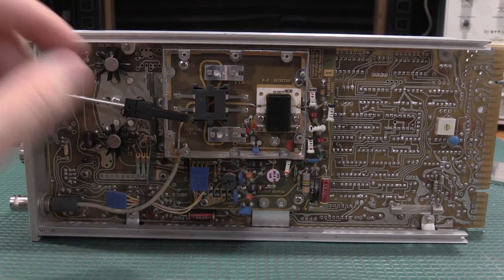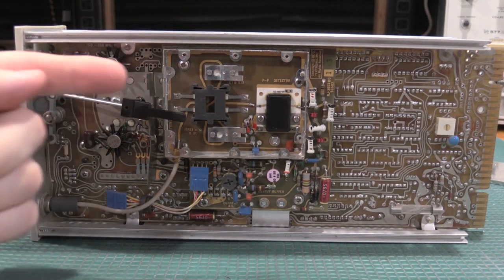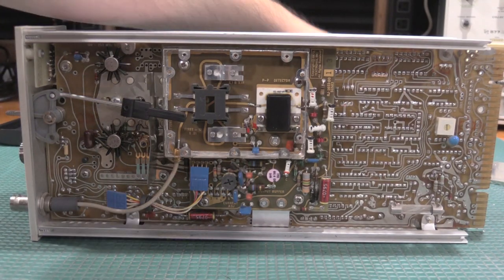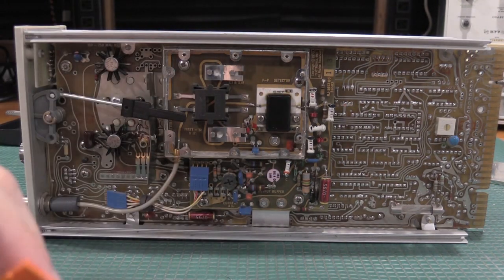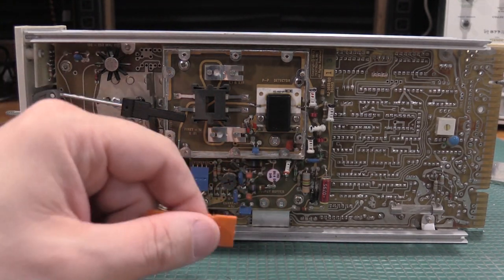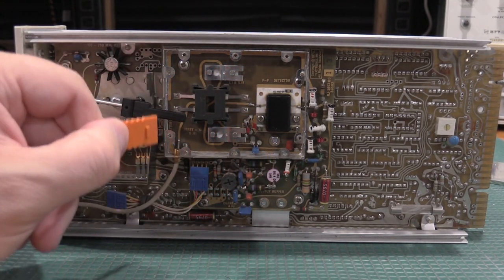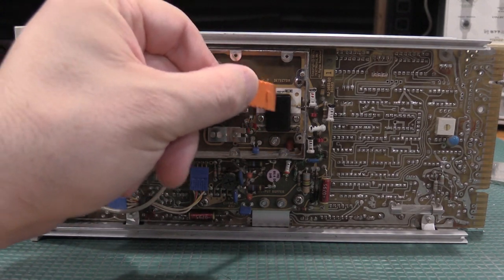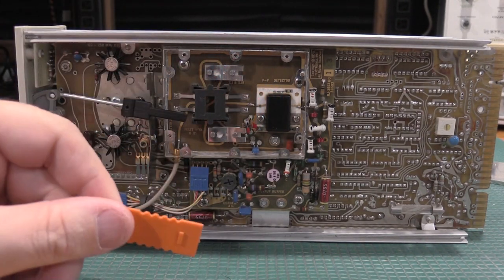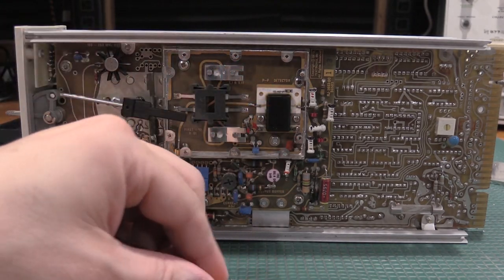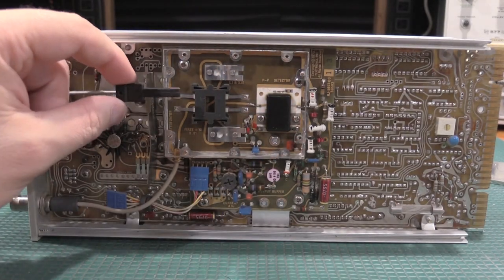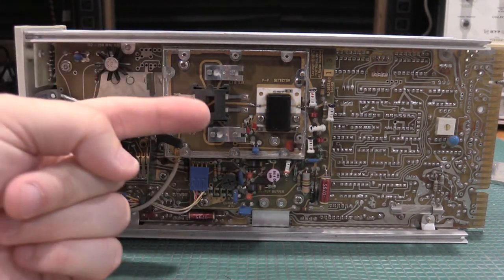Okay. I've got the switches exposed here. This is where that cam switch lever was. That moved that in and out. I did not need to take the peak-to-peak detector board out. You have to be real careful with this board. There's a lot of 50-ohm RF components on this board. This transistor. Given the circuit substrate, it's going to be a fast and exotic part. This is the actual cam switch itself.